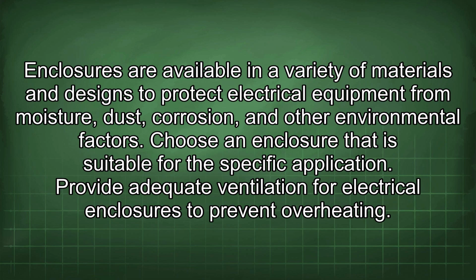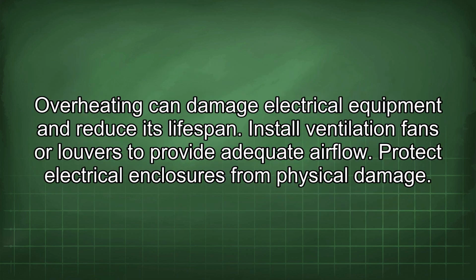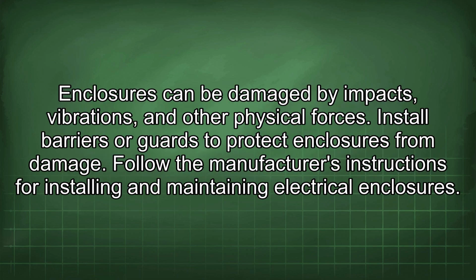Provide adequate ventilation for electrical enclosures to prevent overheating. Overheating can damage electrical equipment and reduce its lifespan. Install ventilation fans or louvers to provide adequate airflow. Protect electrical enclosures from physical damage. Enclosures can be damaged by impacts, vibrations, and other physical forces. Install barriers or guards to protect enclosures from damage.